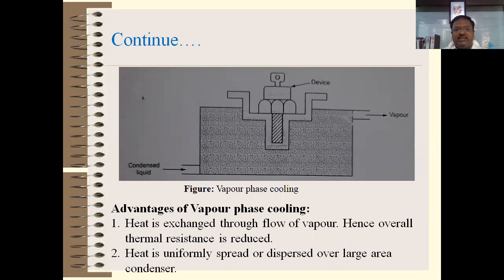If you see, the heat sink is dipped into the coolant, right? Because the heated fins or heat sink are directly dipped into the coolant, the coolant that is used, Freon 113, starts to boil after 47 degrees Celsius and generates a vapor.